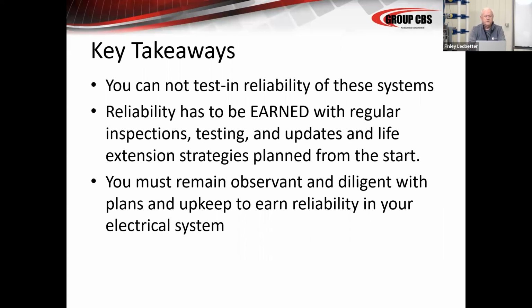The key takeaway should be that you can't test in reliability in these systems. You have to earn that reliability. You do that by doing these maintenance tasks, by doing these inspections. We've just done 25 scheduled 5-year maintenance cycles in this gear to get to 100 years. You've earned reliability because you've done the work. You cannot simply say, hey, I'm going to test it and that's going to make it more reliable. You have to test it on a reliable schedule, and then you have to cycle it through repair and upgrades, and you have to think about all these upgrades and life extension techniques as you go along. You must remain observant and diligent with plans and upkeep to earn the reliability in your electrical system.